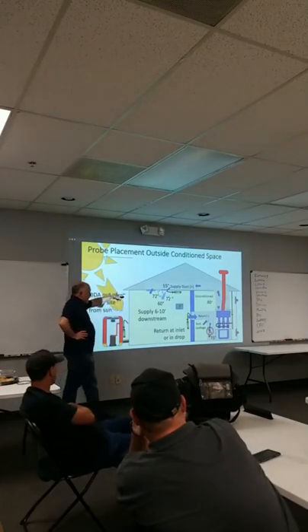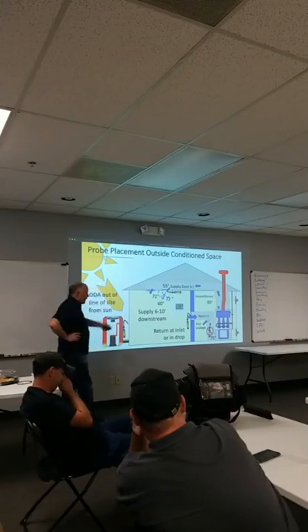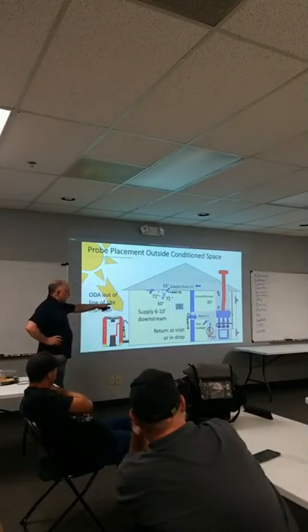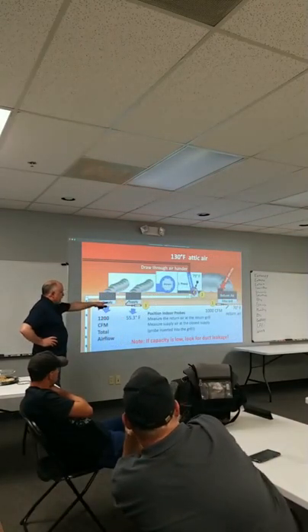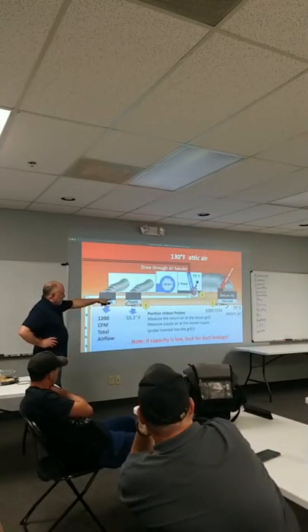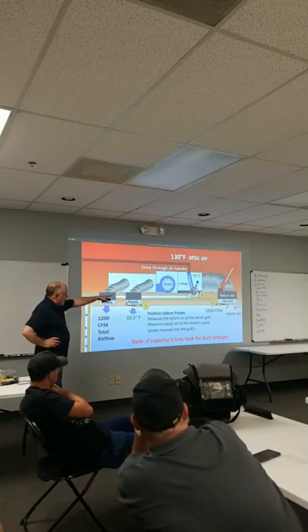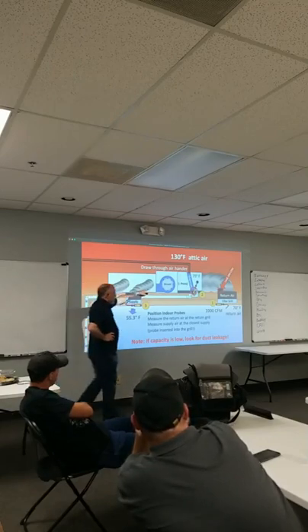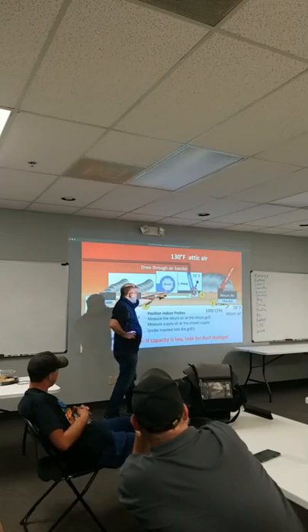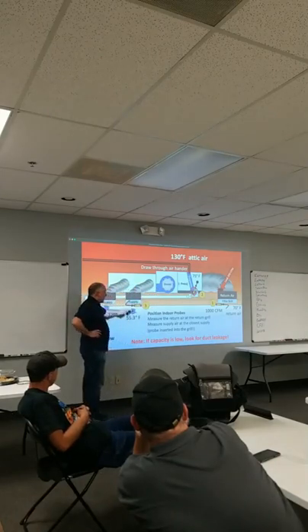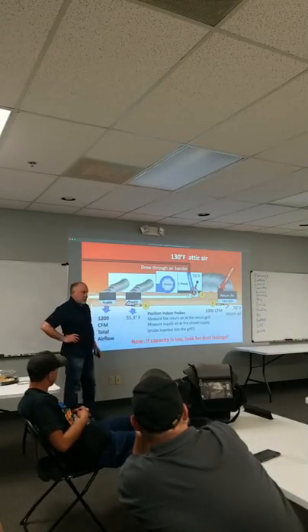So you never wanna measure air temperature at the surface of a register, you actually gotta get it up in the supply duct. We test from the closest return to the closest supply, so we get a good air temperature measurement. Same thing here, right? Again, look at this, you have 70-degree air going in. A lot of guys are gonna put this probe up here in the attic, they're gonna say, oh, I got 75-degree air, 55-degree air, I got a 20-degree split. In reality, the split's only 15 degrees.